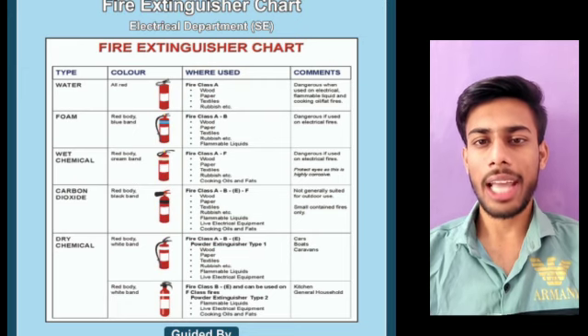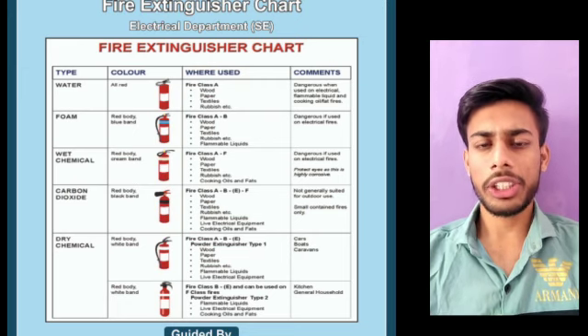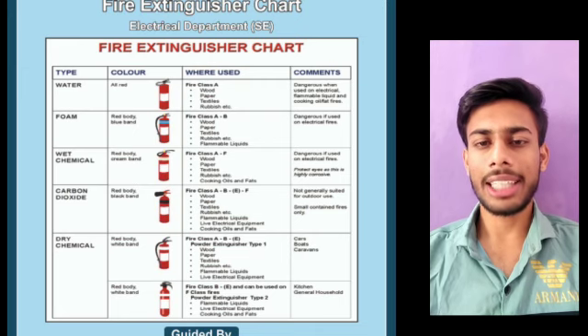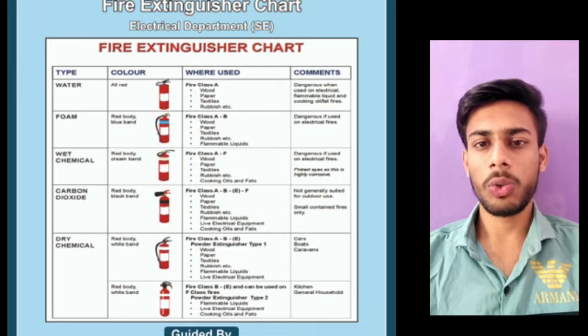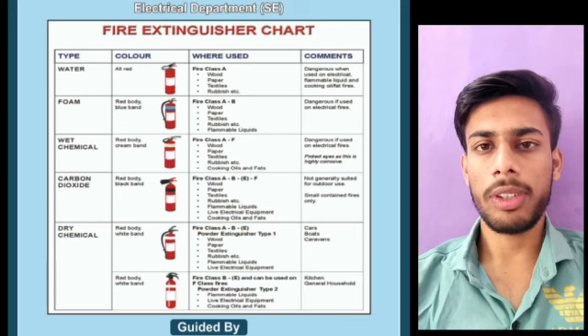The wet chemical fire extinguisher is a new innovation in the fire industry. Its body is red with a cream band. This extinguisher is used for fire class A and F, which involves wood, paper, textile, rubbish, and cooking oils and fats. One advantage is that it is the best fire-fighting medium for fires involving cooking fats.